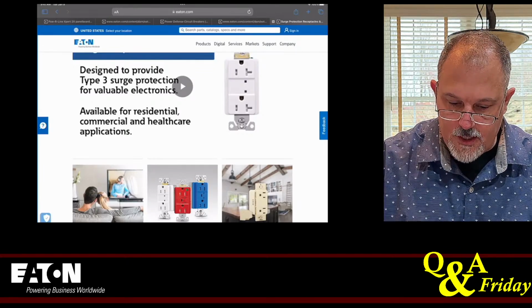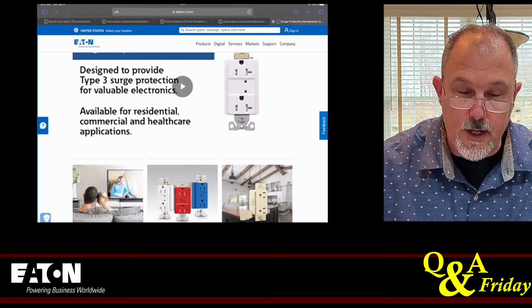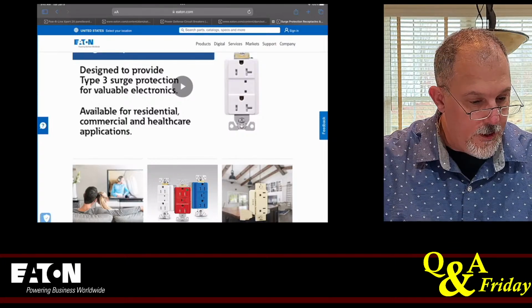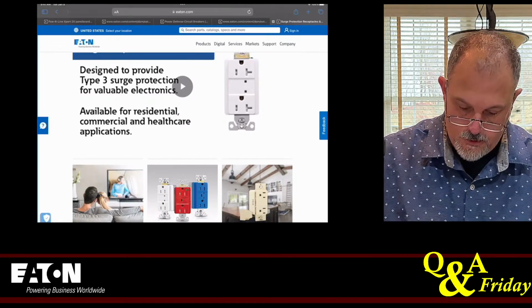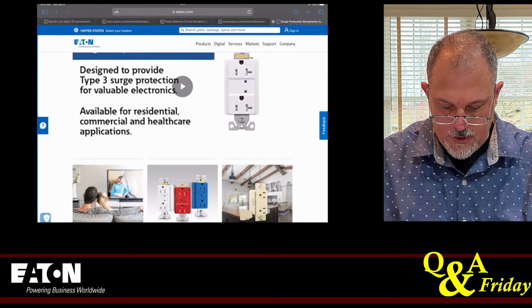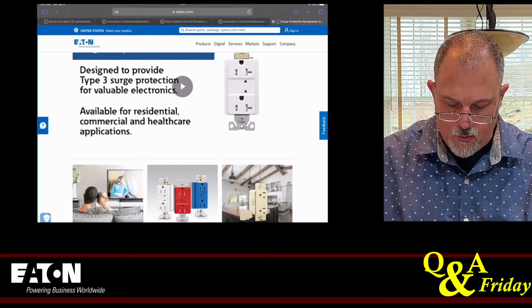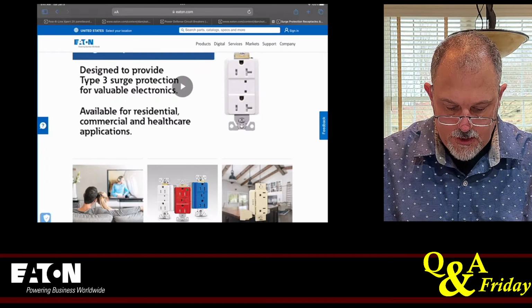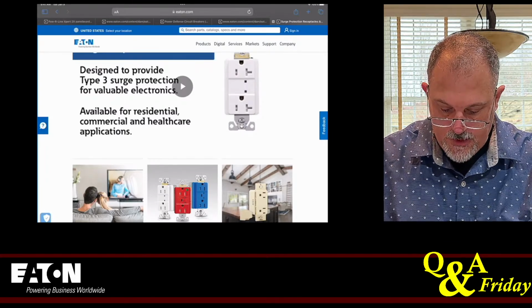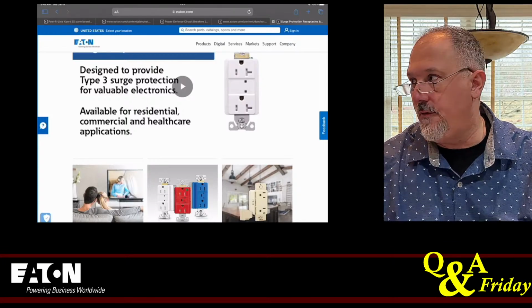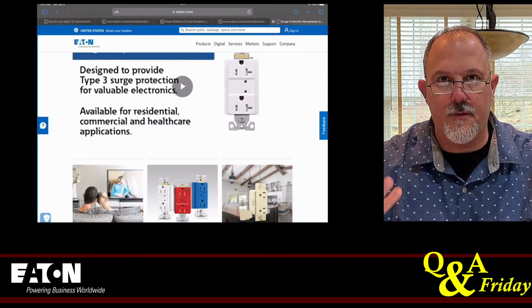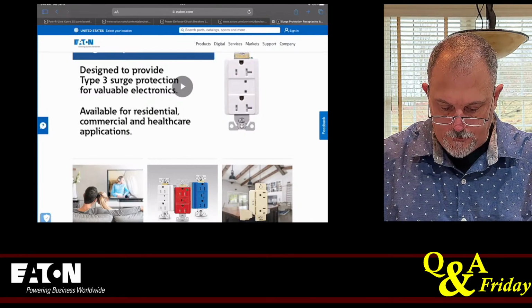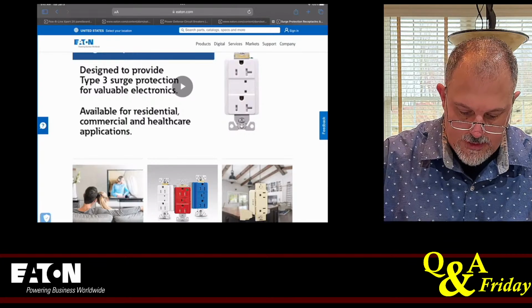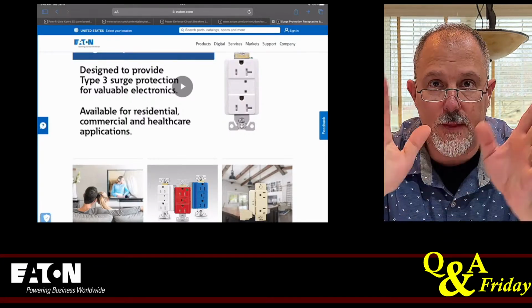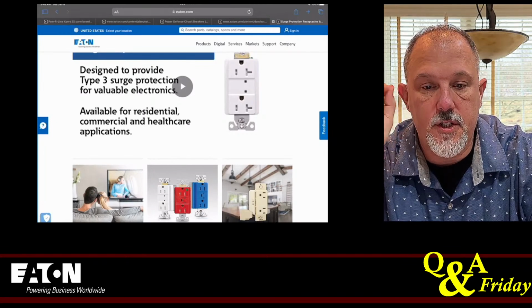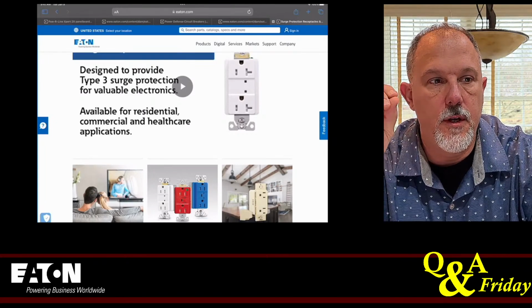So in Article 210, which covers receptacles, and I believe it's 210.21, tells you the maximum cord and plug connected load, receptacle ratings for circuits serving more than one receptacle or receptacle outlet. So 210.21(B)(3) tells you that if you have more than one receptacle outlet, which, if you think about strings, it's as long as it's not a dedicated circuit, you have a surge protection on there, you can put a 15 or 20 amp receptacle on a 20 amp branch circuit. So that's not a problem. And the surge device is not going to cause you an issue.